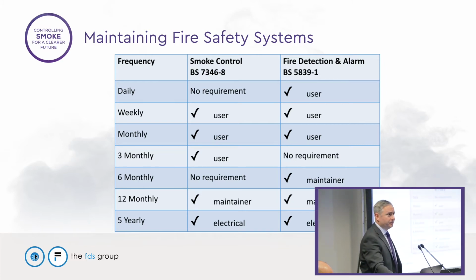You can see in the center column we've got smoke control, and in the right column we've got fire alarms. Most of the time they run pretty much the same, but you'll notice that the daily requirement for smoke control doesn't exist, but for fire alarms it does. And really what they're saying is they're not expecting you to do a fire alarm test every day. They're saying check the system's okay. If you've got a panel on the wall, does it have an alarm status on it? Are the lights flashing? Is it trying to tell you something? And that's essentially what you're looking for.